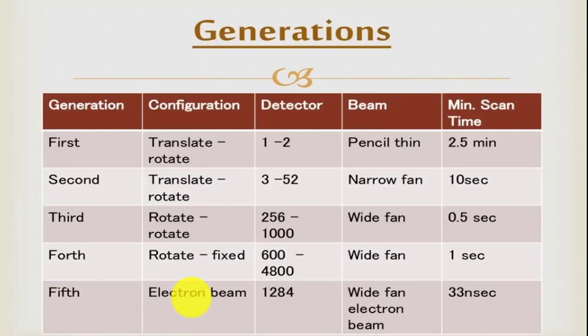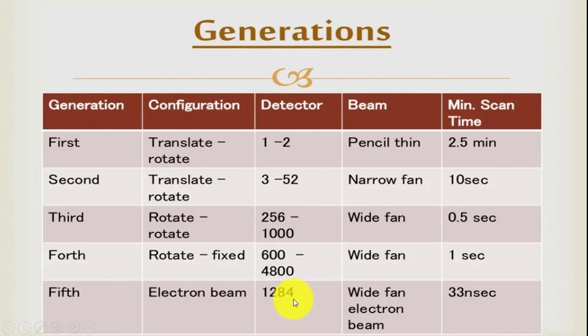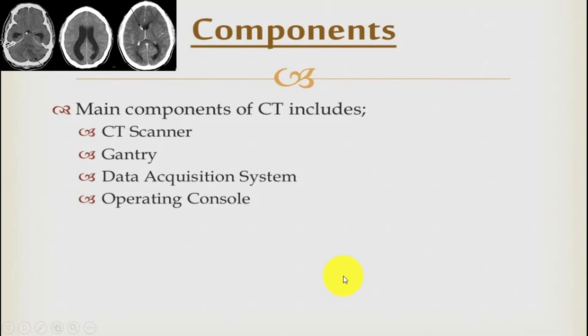These are the generations of CT scan. The most recent is the fifth generation, whose configuration is an electron beam with a scanning time of only 33 milliseconds. It uses 1,284 detectors, whereas the first generation used only 1 to 2 detectors. The components of a CT scan system include a gantry, a data acquisition system, and an operating console.